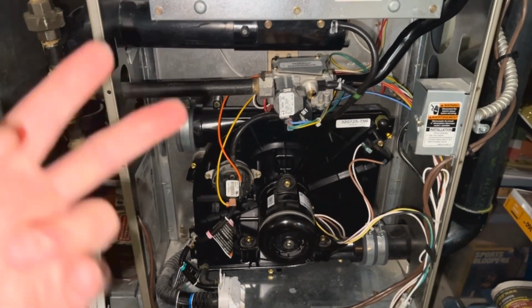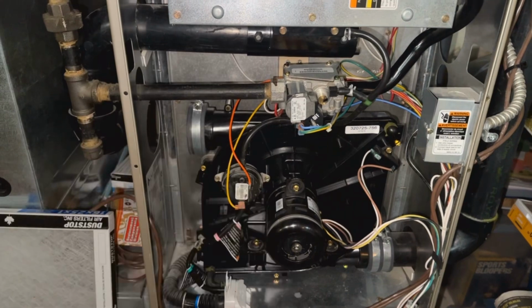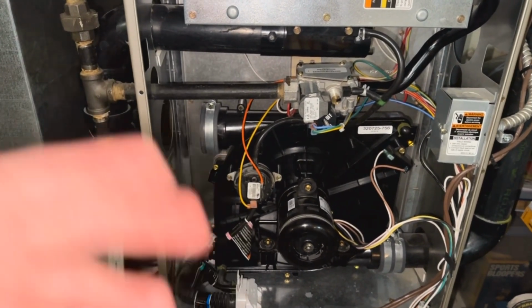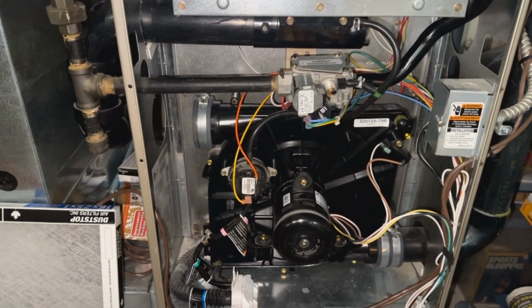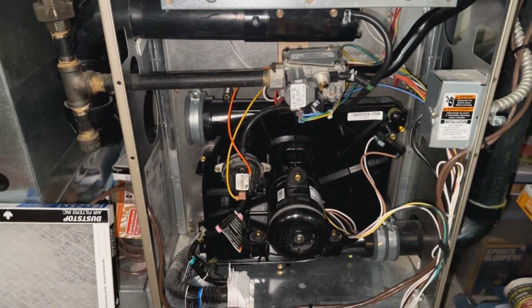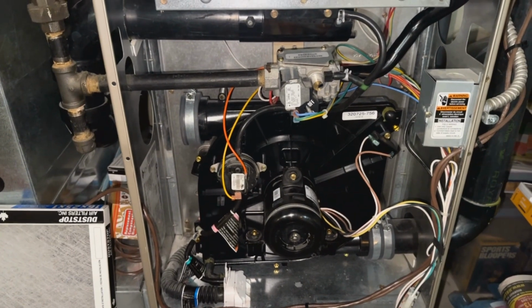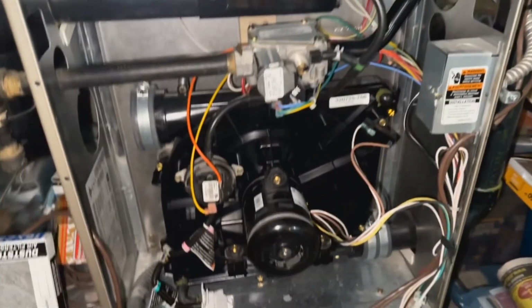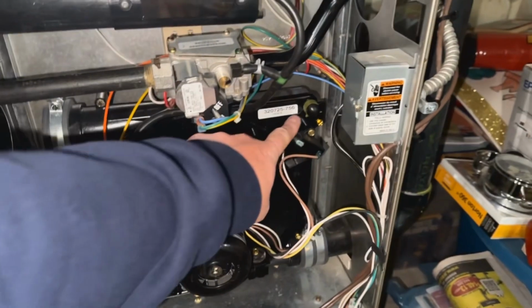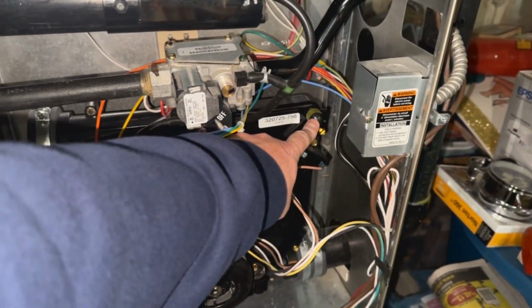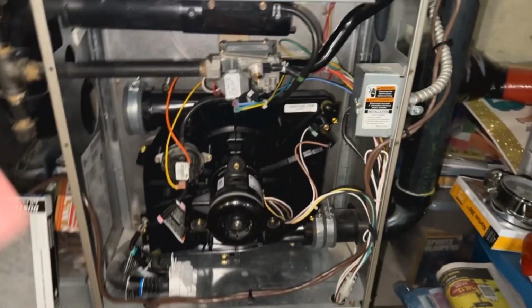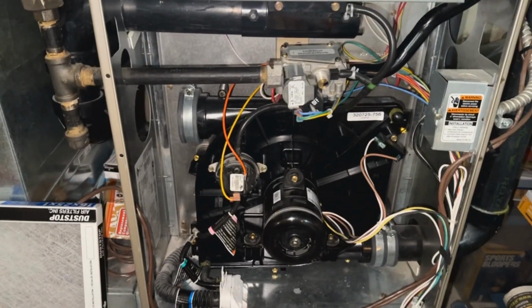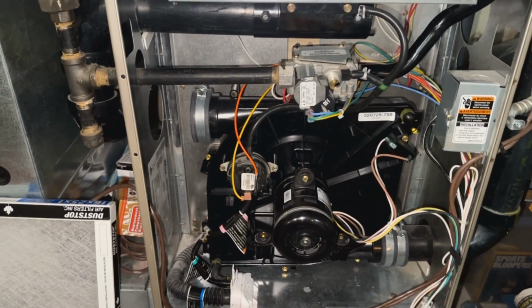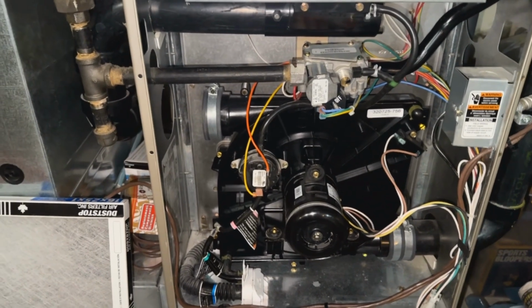When it comes to furnaces, they all have heat exchangers. The high efficiency ones have two, primary and secondary. For this particular model of furnace, the best way to make sure your heat exchangers are not defective is by taking the carbon monoxide reading. So once Paul gets here, we're going to get this thing started up, and he's going to put his probe into this little port here to make sure my carbon monoxide levels are in an acceptable range. Let's see what happens when he gets here.